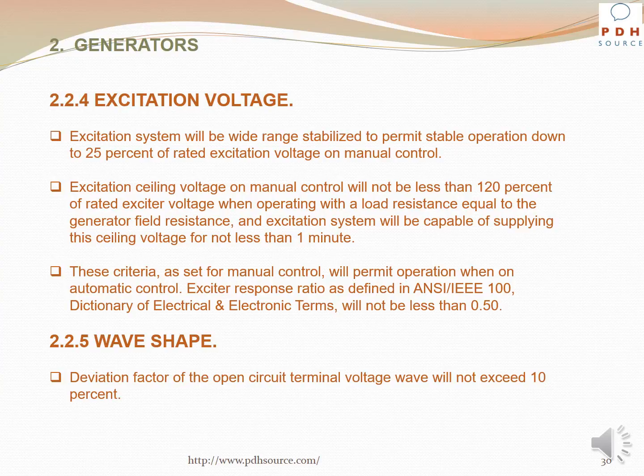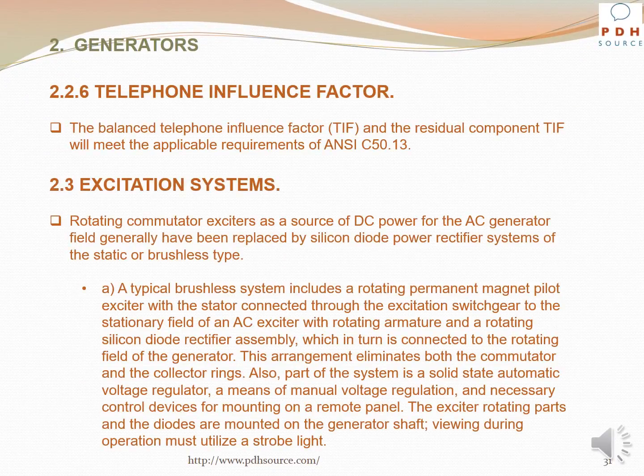Exciter response ratio as defined in ANSI IEEE 100 Dictionary of Electrical and Electronic Terms will not be less than 0.50. Deviation factor of the open circuit terminal voltage wave will not exceed 10%. The balance telephone influence factor TIF and the residual component TIF will meet the applicable requirements of ANSI C50.13.